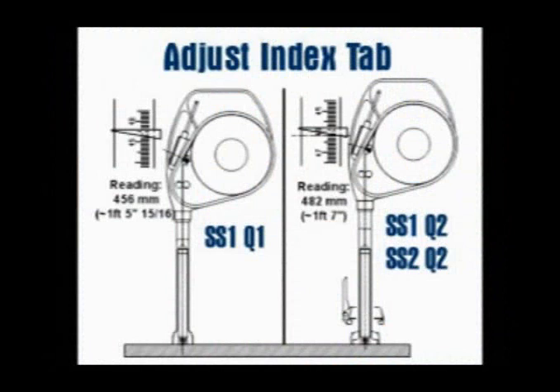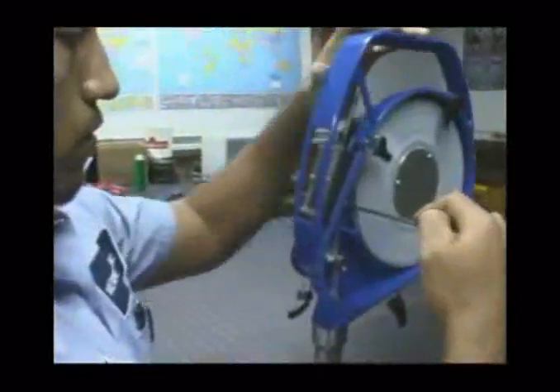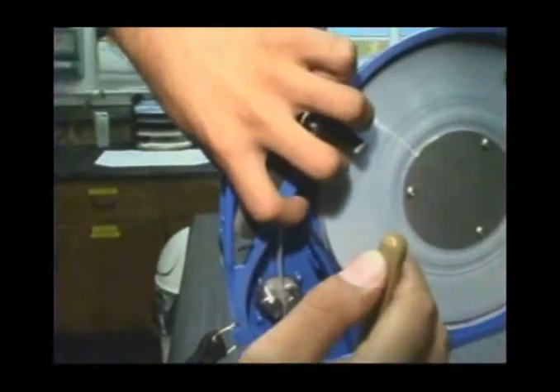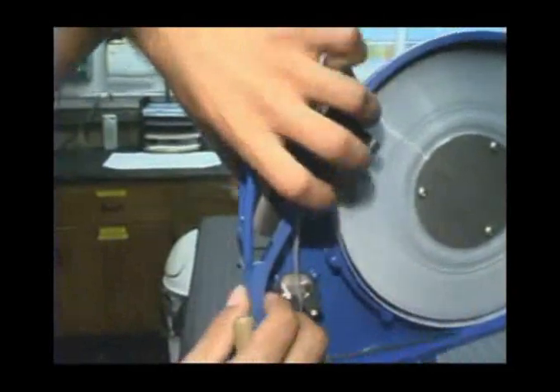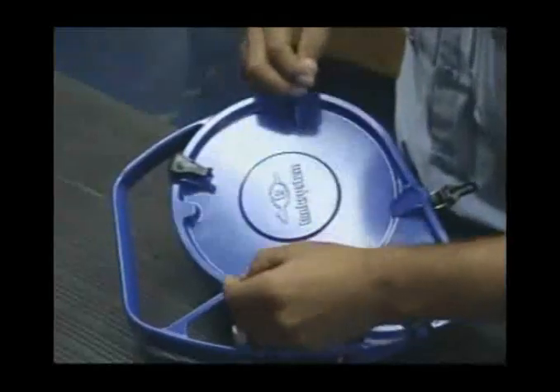For example, the GTEX and RTEX will be set at 456 millimeters with the SS1 storage tube using the Q1 connector, or it will be set at 482 millimeters with the SS1 or SS2 storage tube and the Q2 connector. Once the index block is set and tightened, close the cover and refer to your company instructions to prepare the unit for gauging vessels.